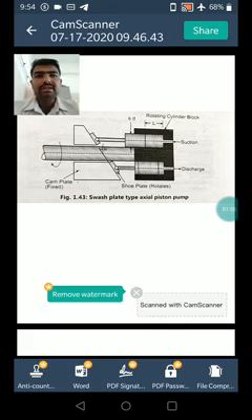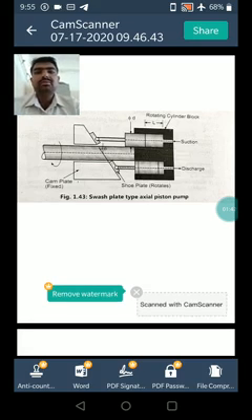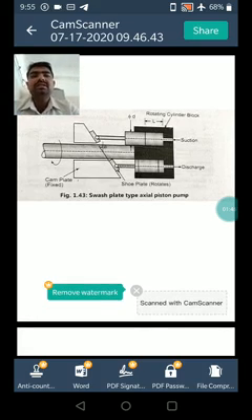It consists of a rotating cylinder block which houses several cylinders. It is mounted on the shaft driven by a motor, with a stationary cam, that is the swash plate, supported on the shaft. It houses several shoe plates, each connected to the piston through the piston rod. As the cylinder block rotates, the piston shoe follows the surface of the swash plate. As the swash plate is at an angle, the piston reciprocates within the cylinder bore.